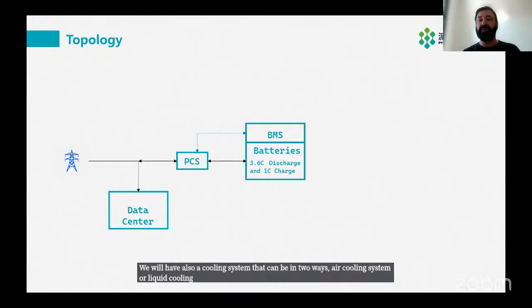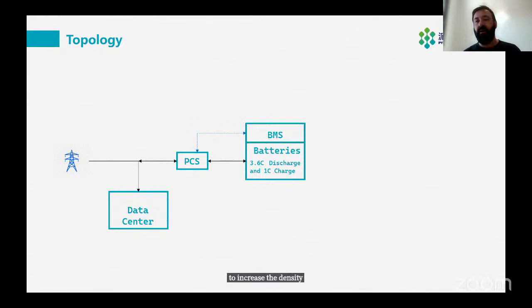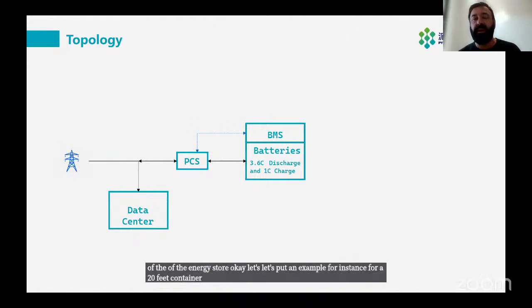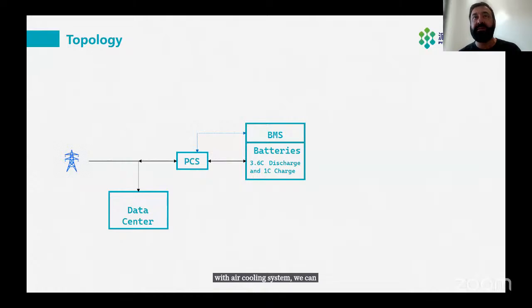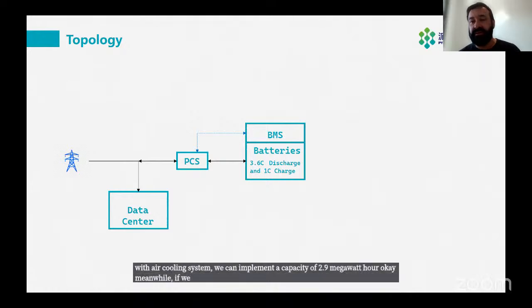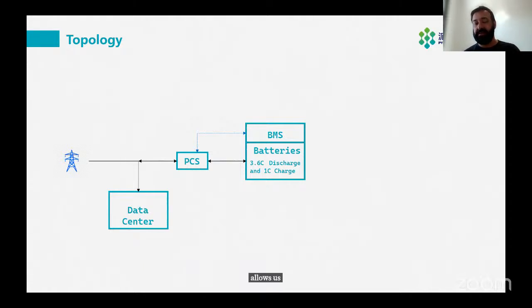Liquid cooling system allows us to increase the density of the energy stored. For example, for a 20-feet container with air cooling system, we can implement a capacity of 2.9 megawatt hour, while with a liquid cooling system we can go up to 5 megawatt hour. This liquid cooling system allows us to increase the energy density of the BESS system.